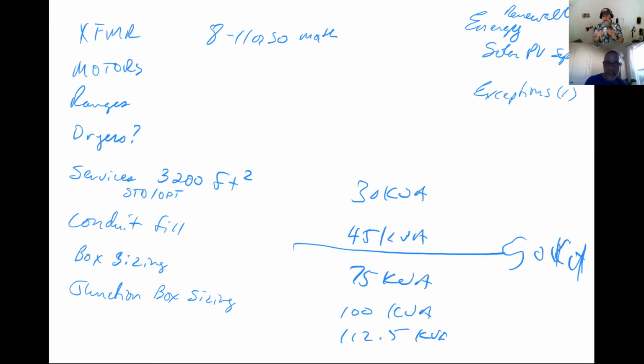Now, I want to also point out that they sometimes play games with the term accessible, especially where it applies to transformers. So this one particularly says, and I'm reading section B, the last sentence, transformers so installed shall not be required to be readily accessible, but they still have to be accessible. So as it applies to equipment, meaning the ceiling assembly has to be removable so you can get in there and do maintenance or connect or disconnect it.